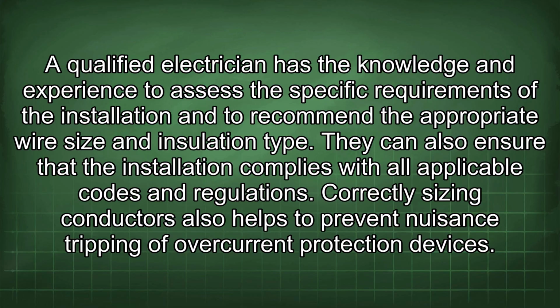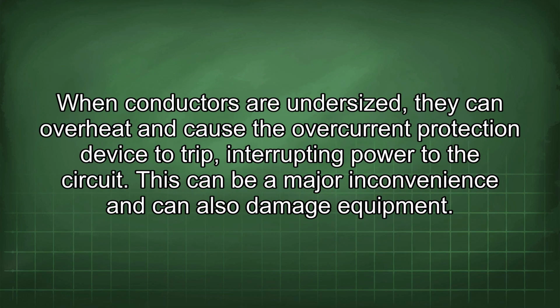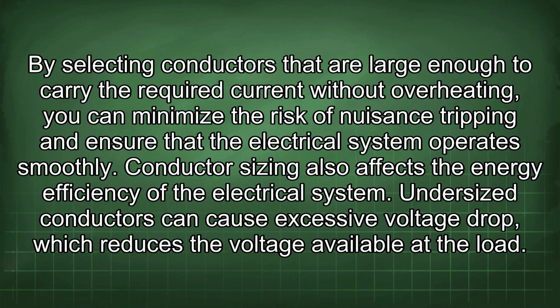Correctly sizing conductors also helps to prevent nuisance tripping of overcurrent protection devices. When conductors are undersized, they can overheat and cause the overcurrent protection device to trip, interrupting power to the circuit. This can be a major inconvenience and can also damage equipment. By selecting conductors that are large enough to carry the required current without overheating, you can minimize the risk of nuisance tripping and ensure that the electrical system operates smoothly.